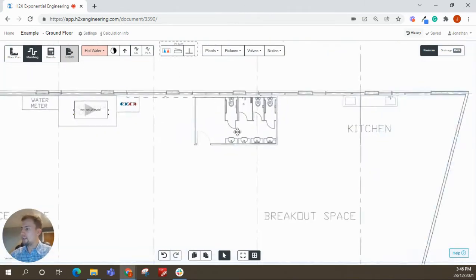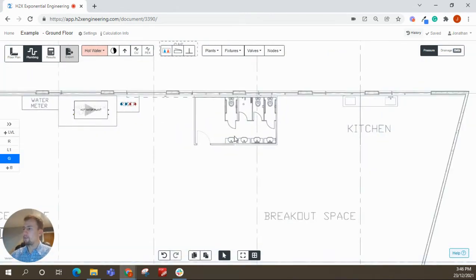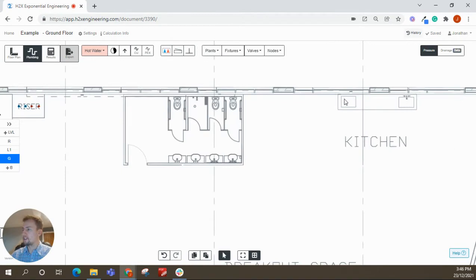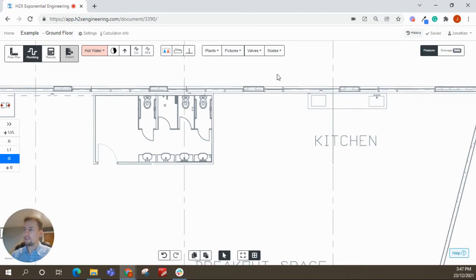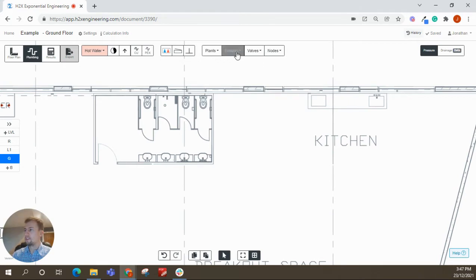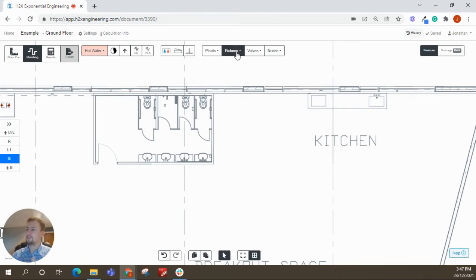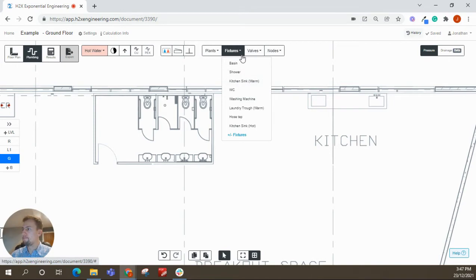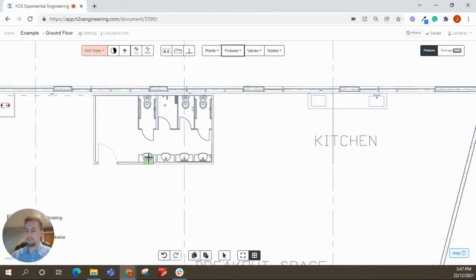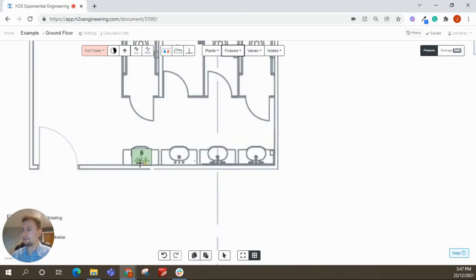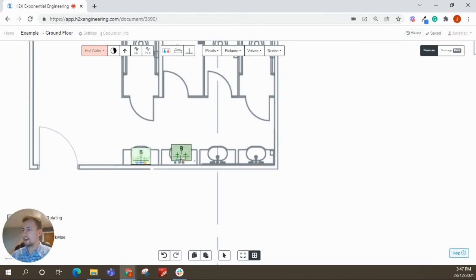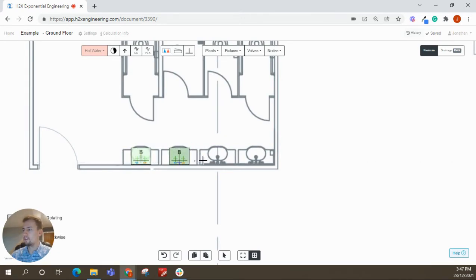All right. And then the next part of it before we start drawing the pipes is showing the fixtures. So there's a couple of ways you can do this. You can show the fixtures or you can show the nodes. Fixtures are good for more detailed designs and nodes are better for like concept designs. So I'll just as an example, I'll do the fixtures on ground floor and we'll do the nodes on level one. But the way it works, just pick your fixture here. So basin, rotate with the arrows on the keyboard. And you just want to place this on top of where the architect shows them. So we've got these four here.